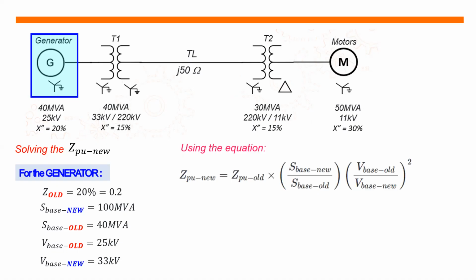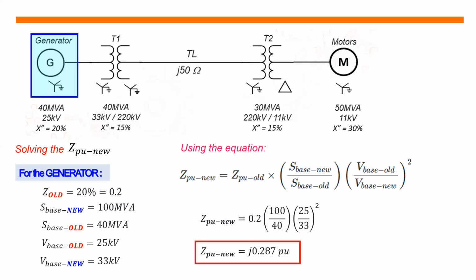So using the equation, we will just substitute all the given values. That will be 0.2 multiplied by 100 over 40 multiplied by the square of 25 divided by 33. And we will get the new per unit impedance is equal to j0.287 per unit.